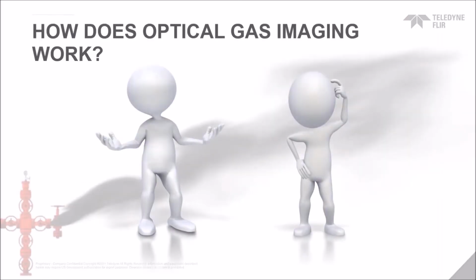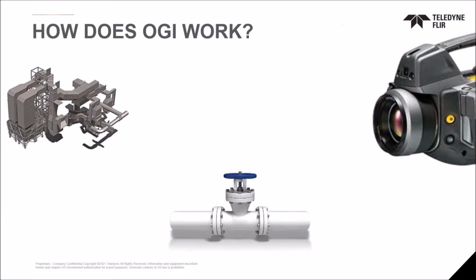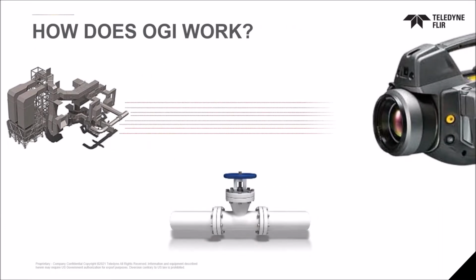How does optical gas imaging work? I don't want to get too much into this, but for those of you that may be new to the technology, simply put, an infrared camera, an optical gas imager, has energy from a background that is actually going into the camera itself. The majority of the time, unless you're looking at the sky, anything else that actually has energy in it, that's not negative energy, that energy is moving from whatever it is into the camera.